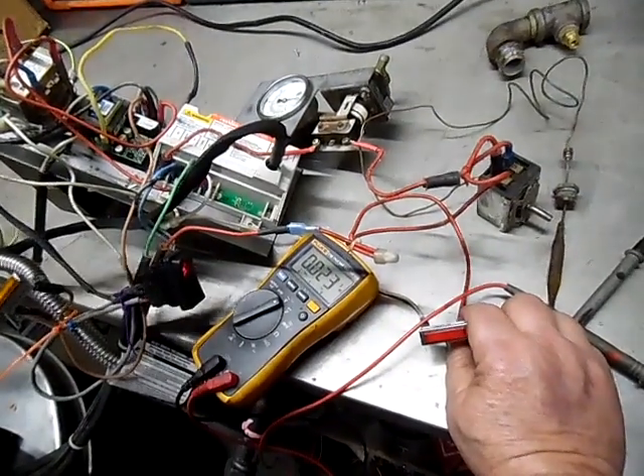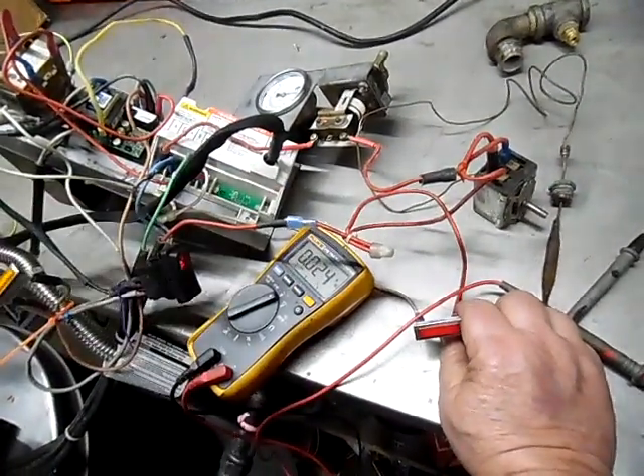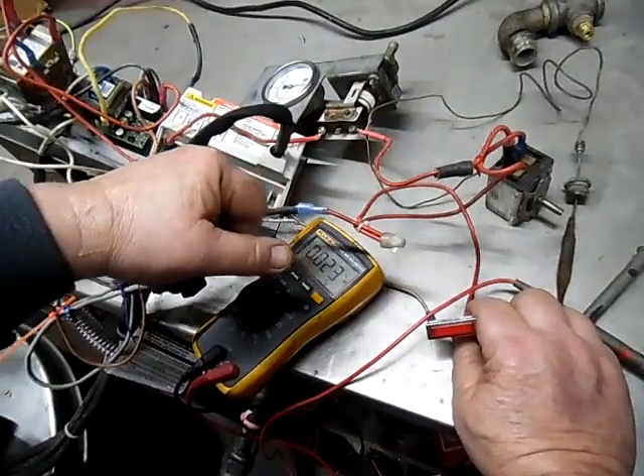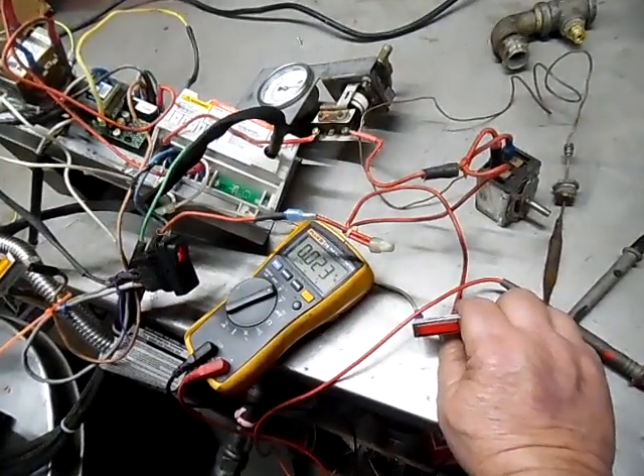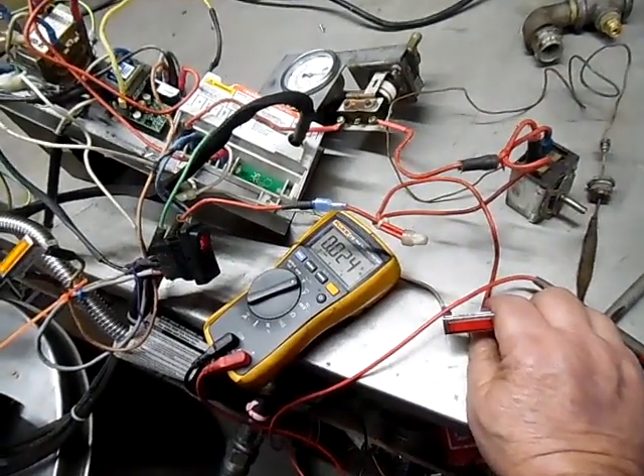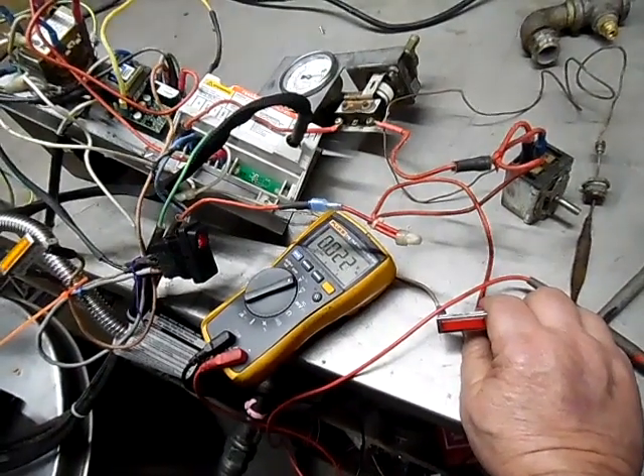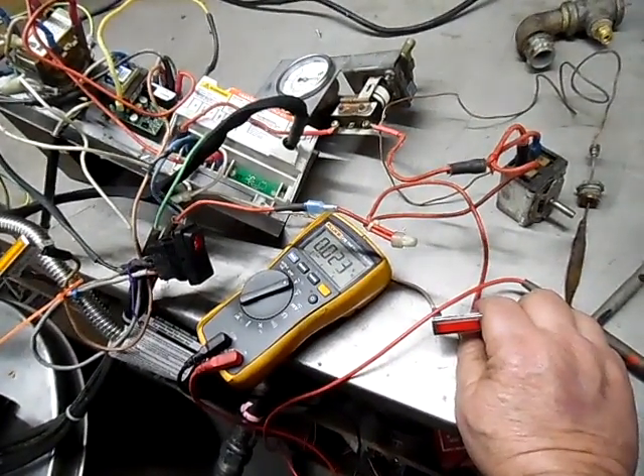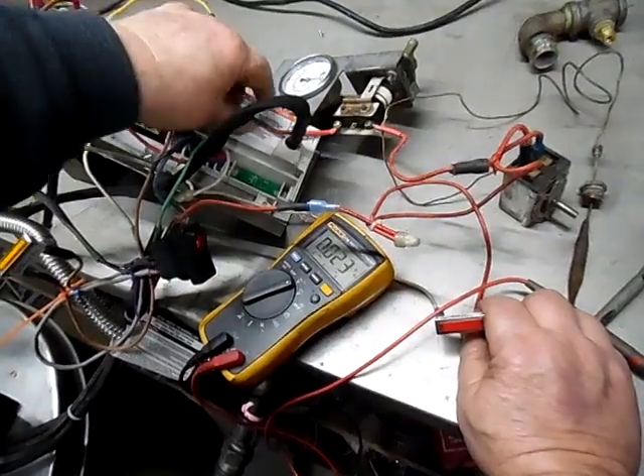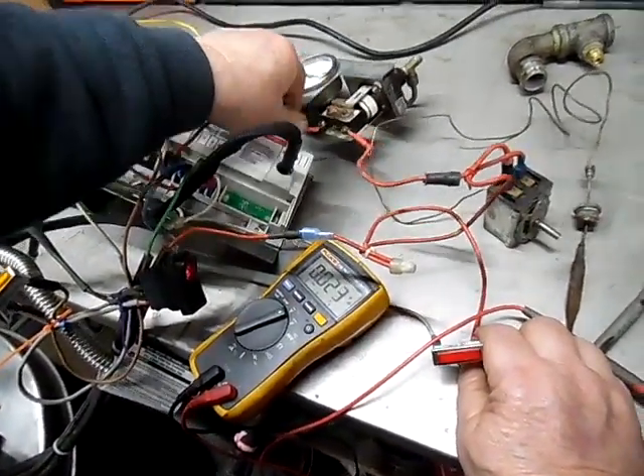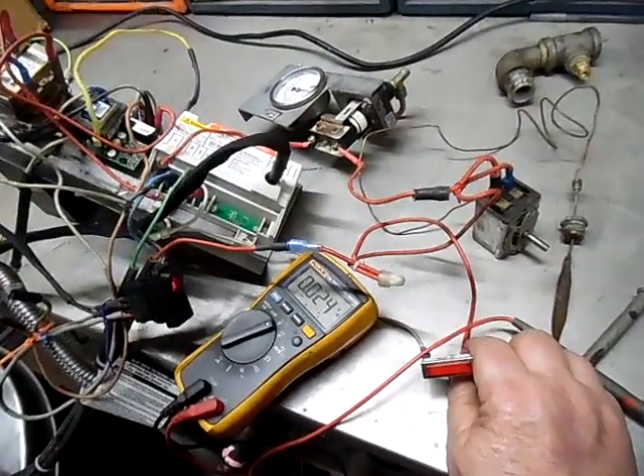I'm seeing a lot of machines that have the single rod systems now going to extra grounds, because as the machines get dirty and get old, and you can't get to these pilots that well, they're losing that rod, the microamps are dropping. And once it gets to a minimum, this box will go in and out. And you will chase your tail if you're looking for other components on it.